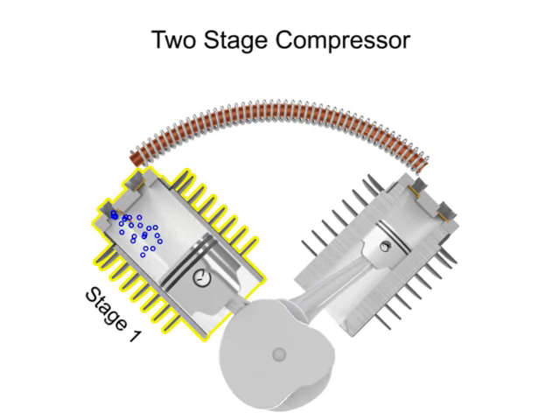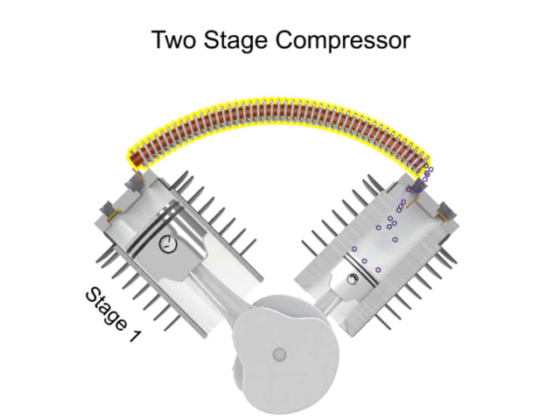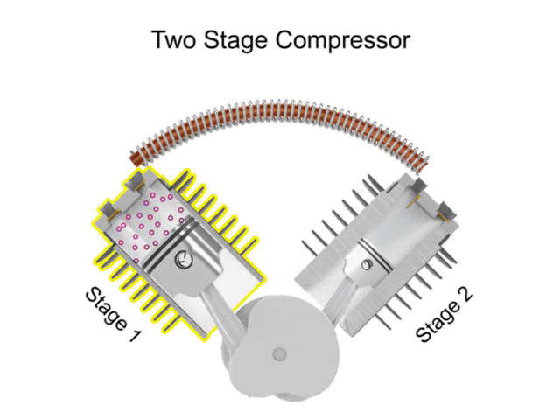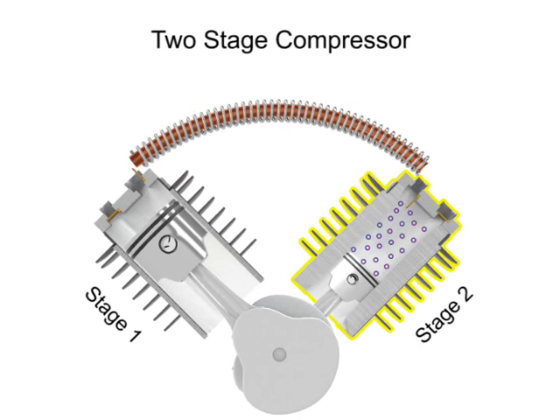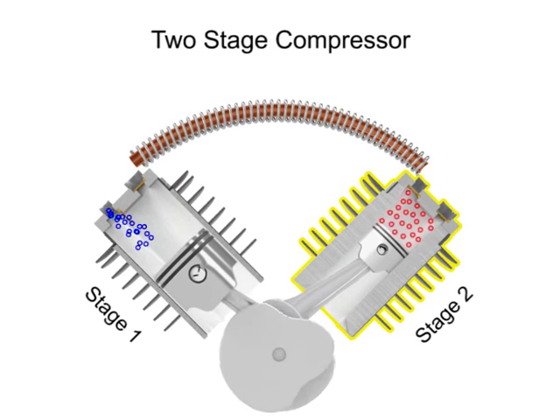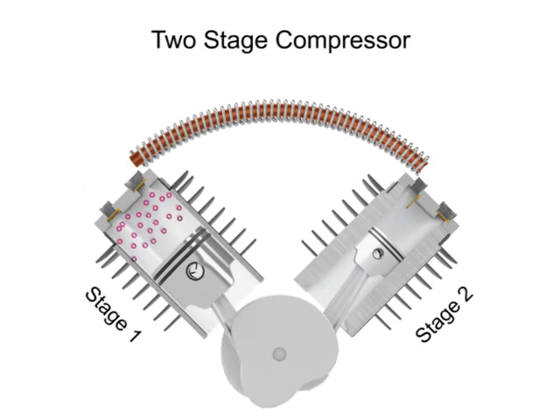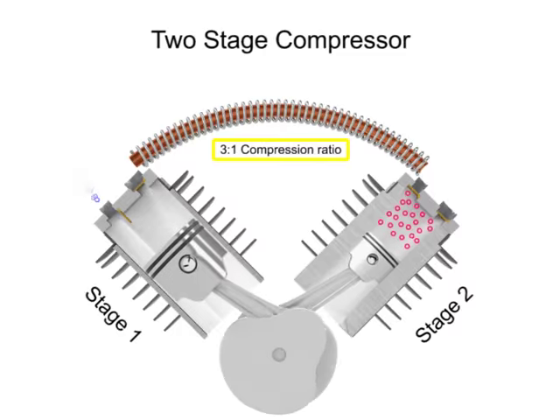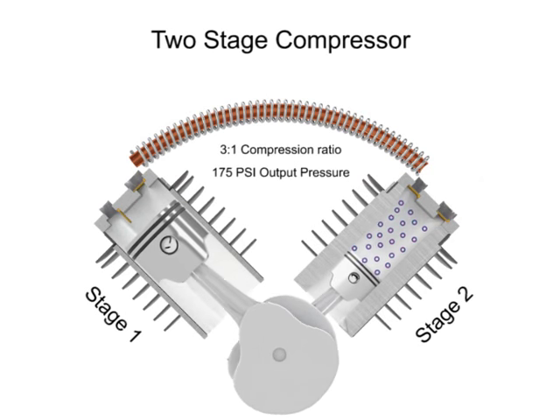The air is compressed in the first stage, which is typically the largest stage, then cooled, then compressed in a second stage. The hot compressed air from the first stage is conducted to the second stage through finned tubing exposed to air from a flywheel fan. After cooling, the compressed air enters the second stage to be compressed even further — this is sometimes called supercharged air. Two stage compressors have a compression range of 3 to 1 or less per stage, but can operate up to 175 psi, and can deliver more air at a higher pressure than single stage compressors of the same horsepower.